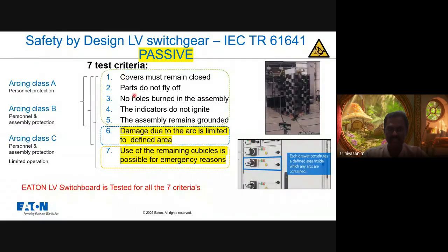Criteria number 1 says that during the internal arc test, they will take a small piece of wire, like a 1 mm diameter wire, and make a short between the two live phases. When they inject the power, the external doors or covers should not open, and none of the parts should fly off from the switchgear towards the outside. They will also keep a small cloth around the switchboard at 1 foot distance. What you are seeing, this black color square, is a cotton cloth, and it should not catch fire in the event of an internal arc.